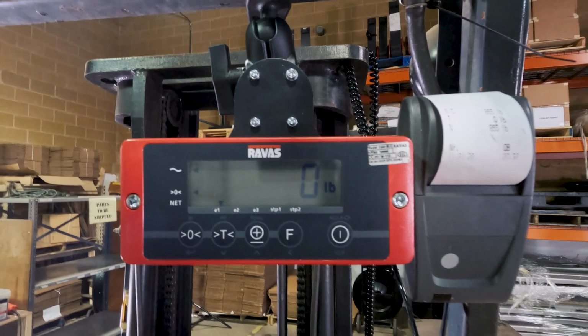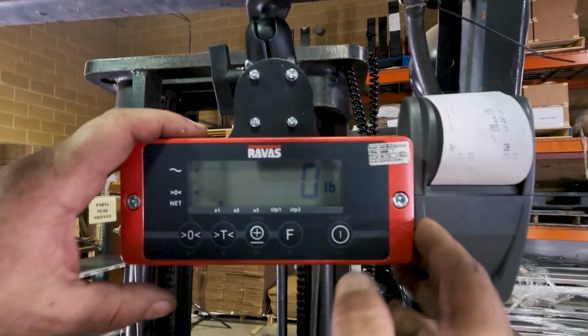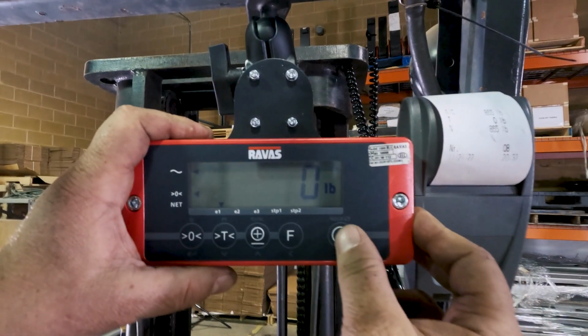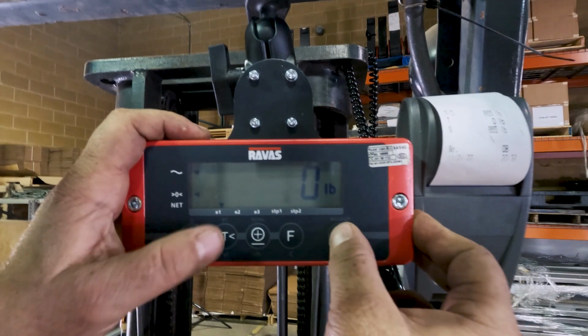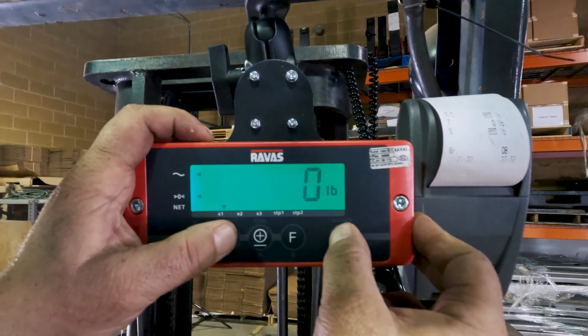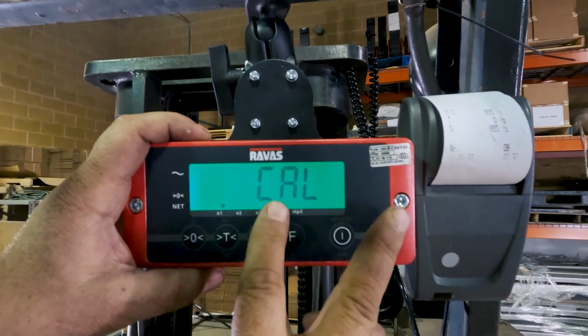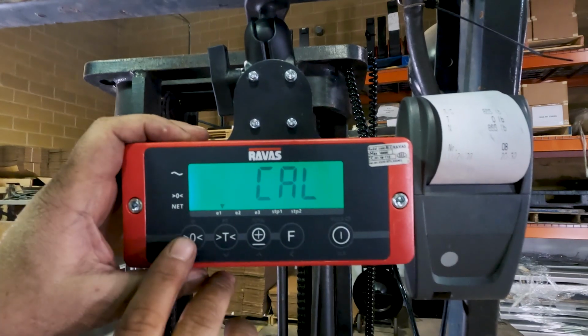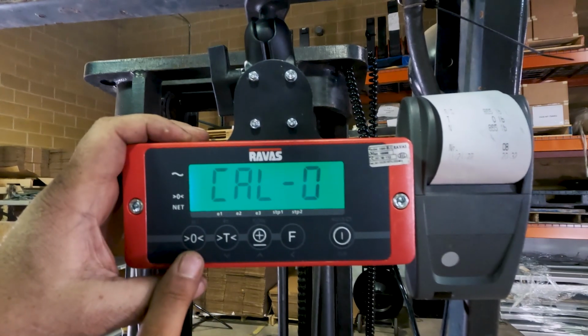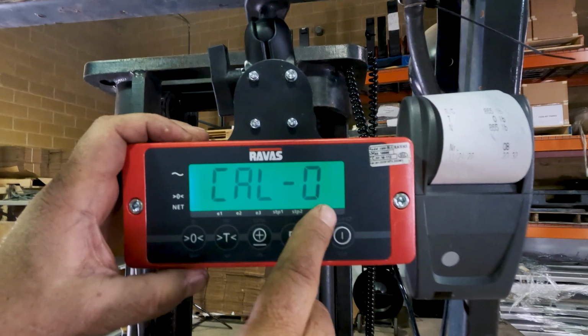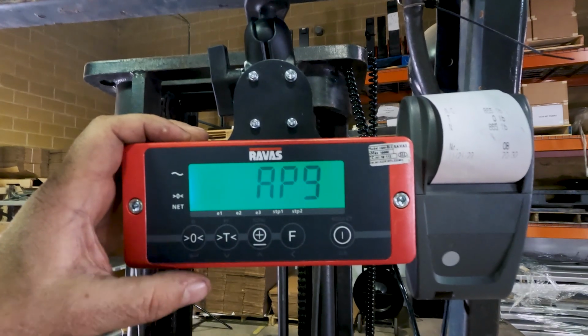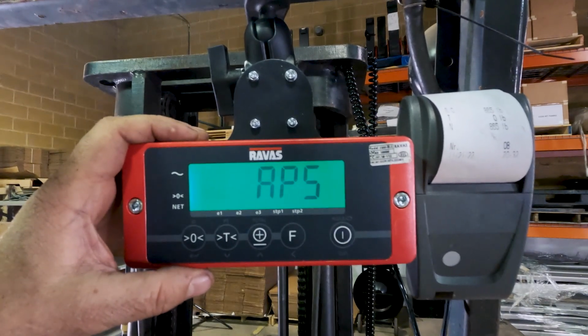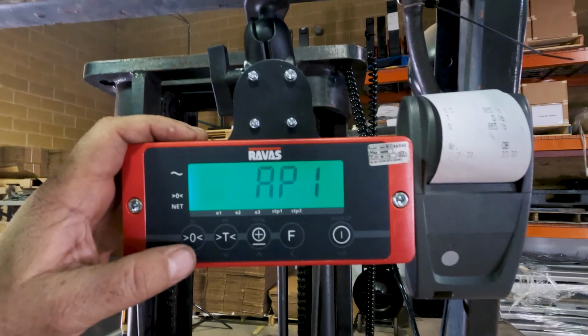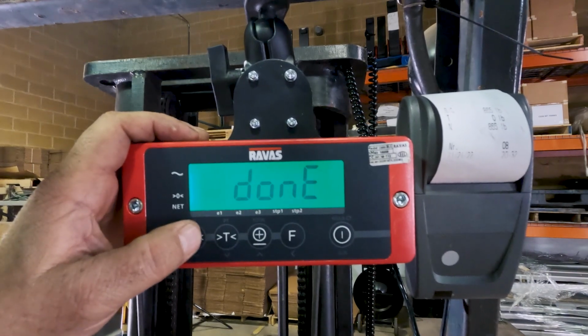We will start with the 0 calibration. To enter calibration mode, you will press and hold the power and the T button simultaneously till it says cal or calibration. Once we hit enter, our first option is the calibrate 0 mode. We will hit enter, let it count down. Once it says done, we will press and hold enter until it says set. This locks it into the system.